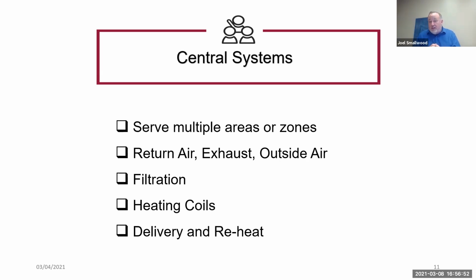So it monitors all kinds of things. It monitors individual room temperatures, so individual boxes inside the big box. It monitors CO2 levels. Usually that happens in the ductwork that leads to and from the system. It monitors the different zones in the system individually. It monitors outside air, monitors humidity outside the building. It's pulling in a whole bunch of data. It also monitors several different points inside that central system, that big air handler I talked about.